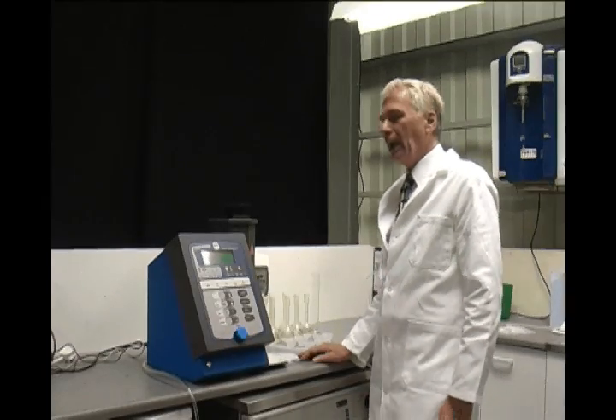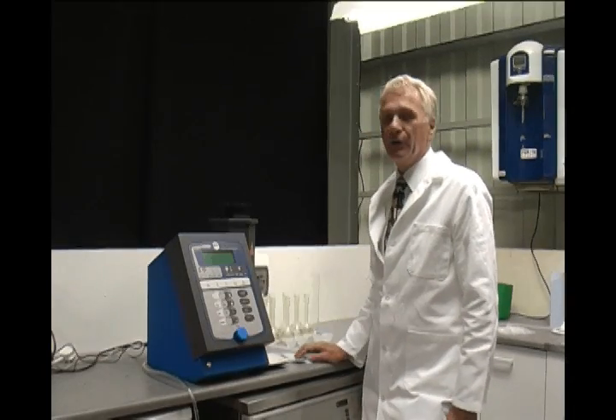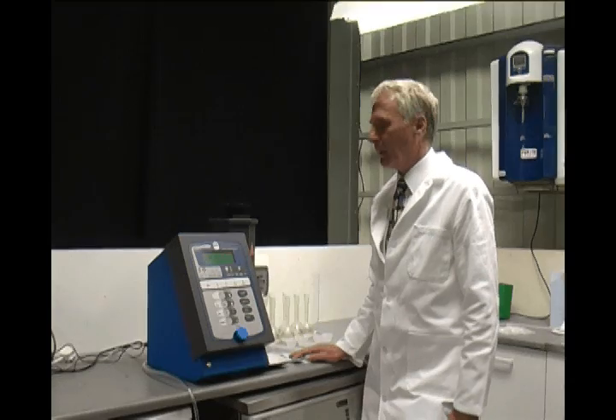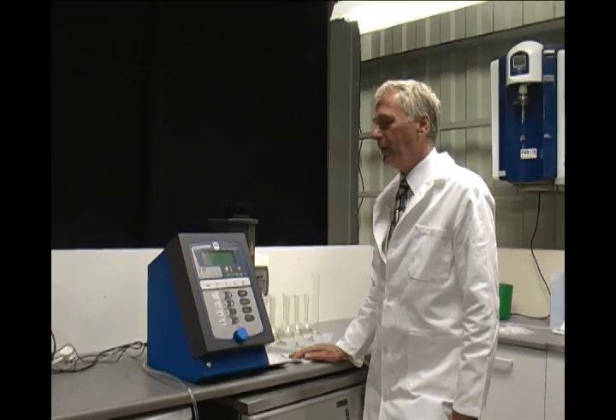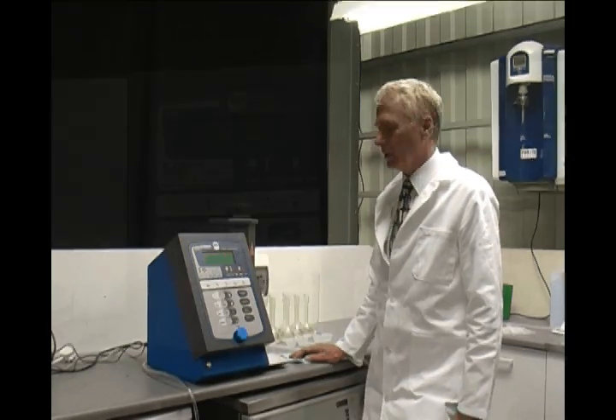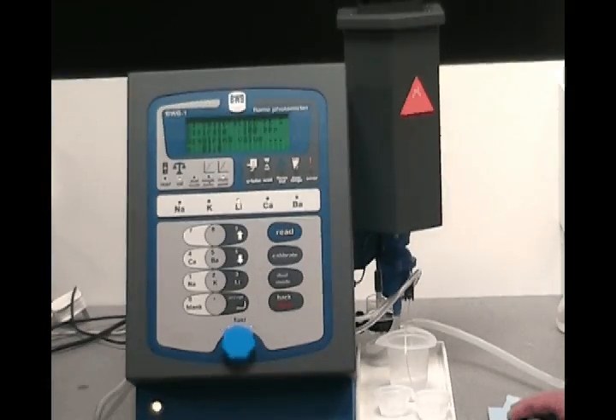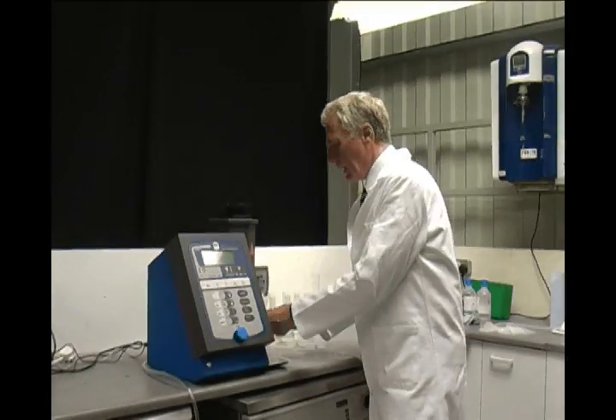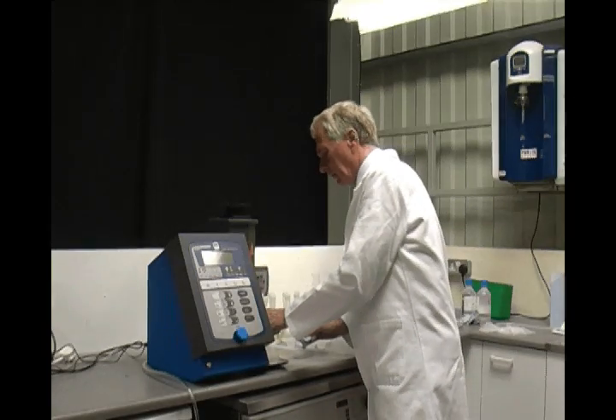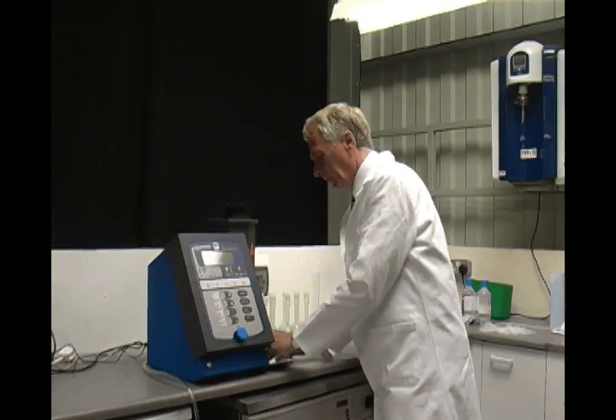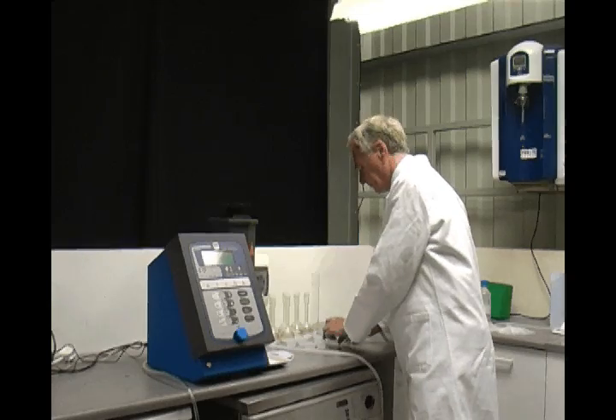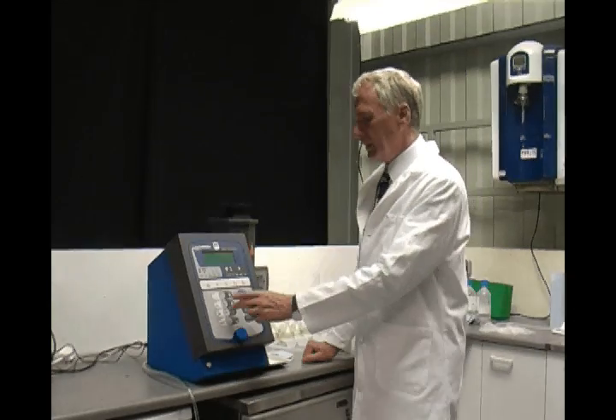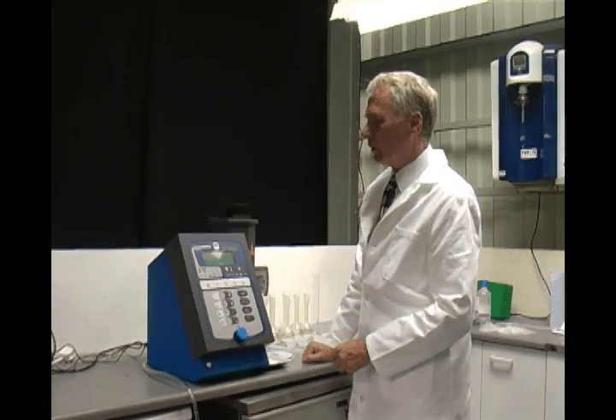And in a few moments we will perform a calibration for 3 different ions at 2 points, plus blank, and that will give us a very good basis to do some measurements. That's it, we now have our system calibrated. I'll just return the aspiration tubing to the blank, and we can now go and view our calibration.